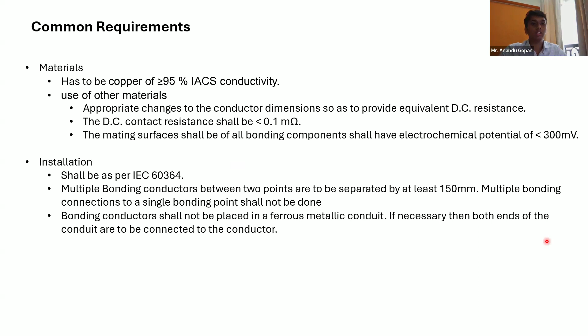So first, you have your racks, server racks, data racks. Basically it's the same, and you have your equipment. For this equipment, you have something called an RBC, which means a rack bonding conductor. You are going to connect all the metallic parts in your rack to a single conductor or a single bar, and you are going to take it outside. And when you take it outside, you'll go and connect to another point, which I'll explain in the upcoming slides.